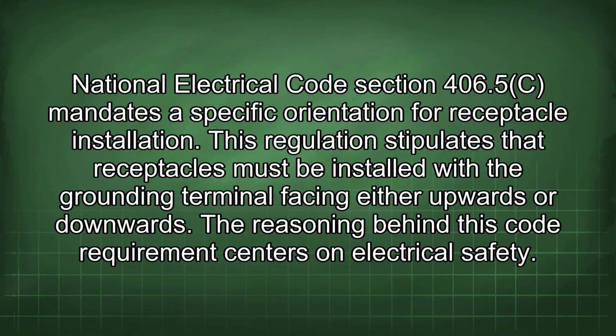National Electrical Code Section 406.5c mandates a specific orientation for receptacle installation. This regulation stipulates that receptacles must be installed with the grounding terminal facing either upwards or downwards. The reasoning behind this code requirement centers on electrical safety.